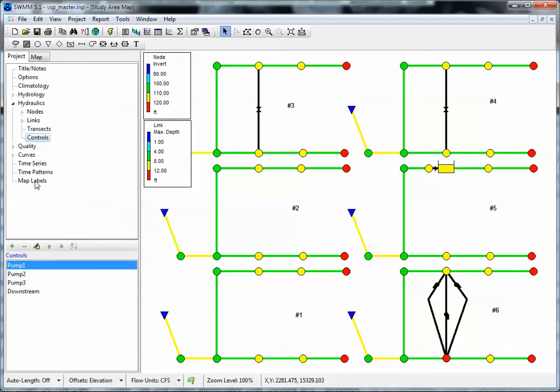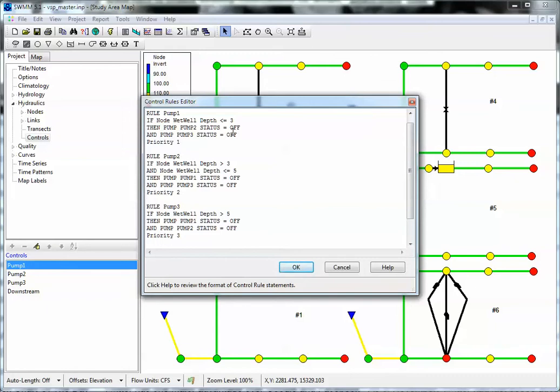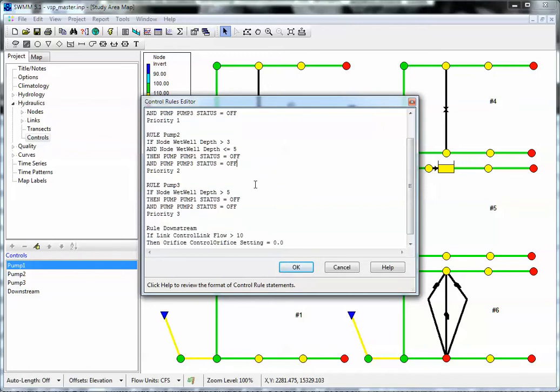There are also rules you can have in SWMM 5. The first rule is: when pump 1 is on and the wet well depth is less than 3, turn off pumps 2 and 3. Then when the depth is between 3 and 5, turn off pumps 1 and 3. And when the wet well is greater than 5 feet, turn off pumps 1 and 2.